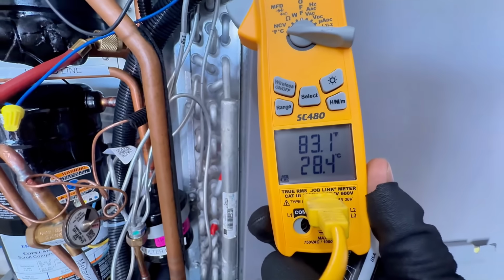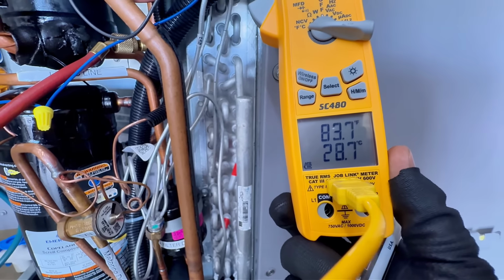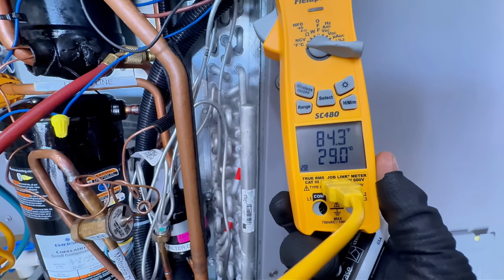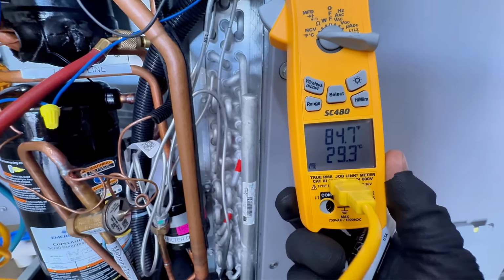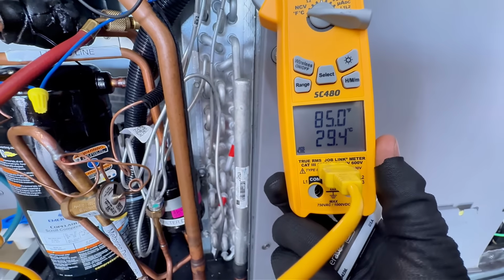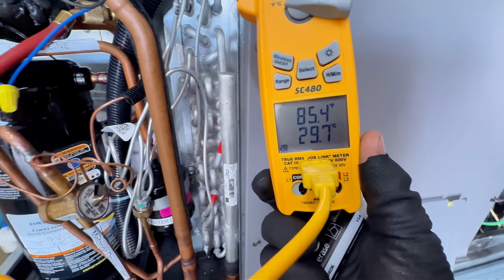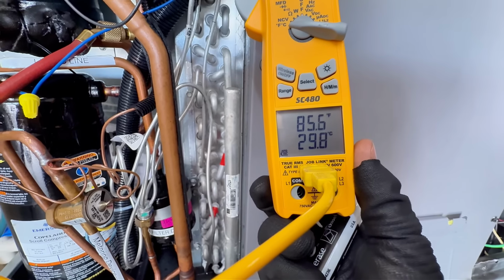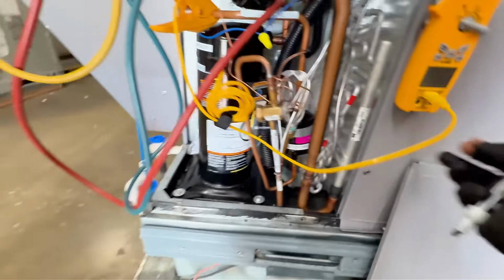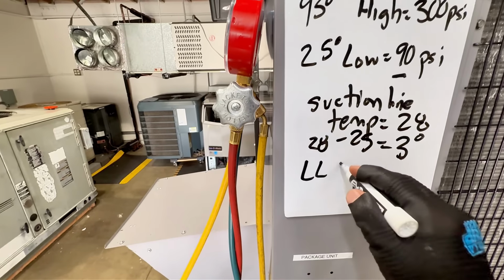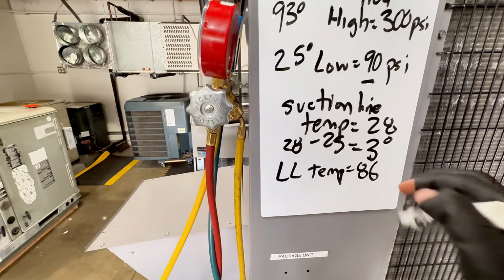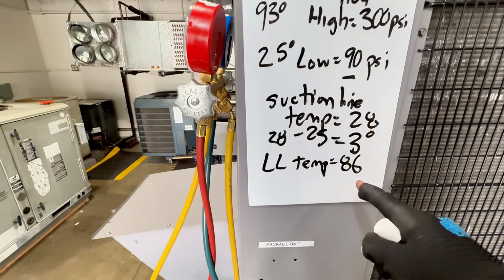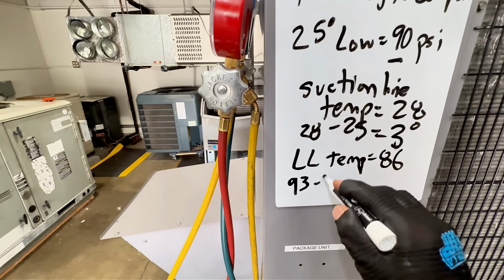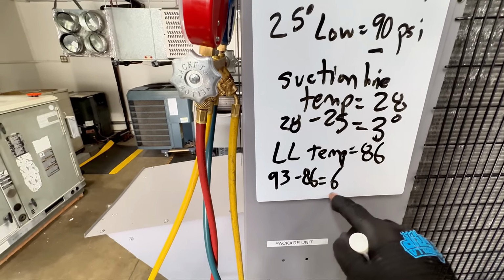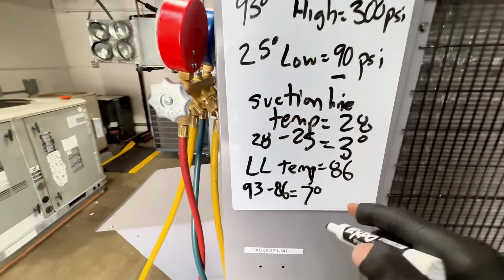Okay, it's climbing up to 83. Let me see, 84, and it's kind of stopping there somewhat. I want to give it a couple seconds. 85, it stopped at 85. Let's see, 85.4, and it's going to be changing a bit. Okay, there we go, 86. So liquid line temperature is 86. Remember your subcool: it's condensing temperature minus your liquid line temp. So 93 minus 86 is 7 degrees of subcool. Okay, right away, I know we have an airflow issue.